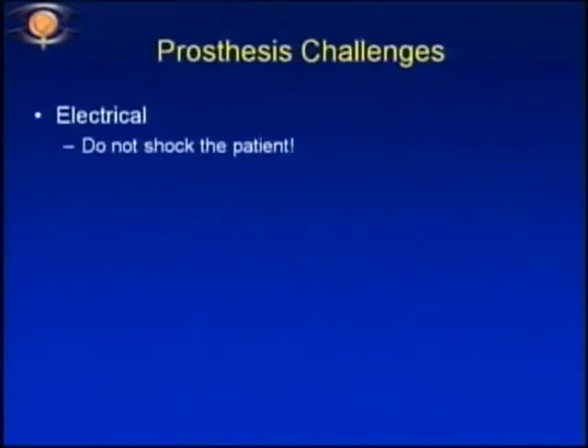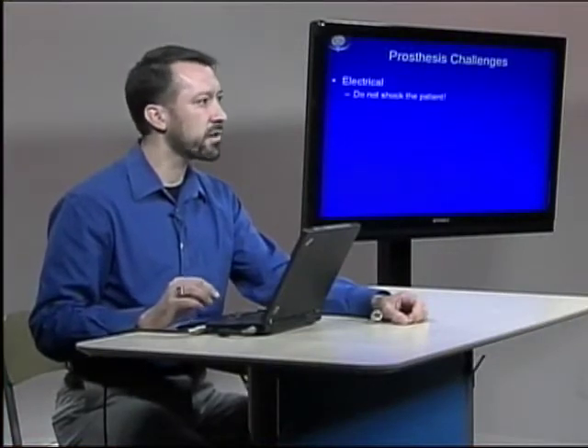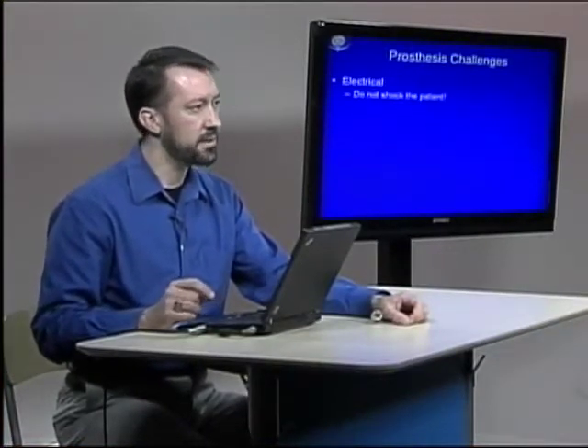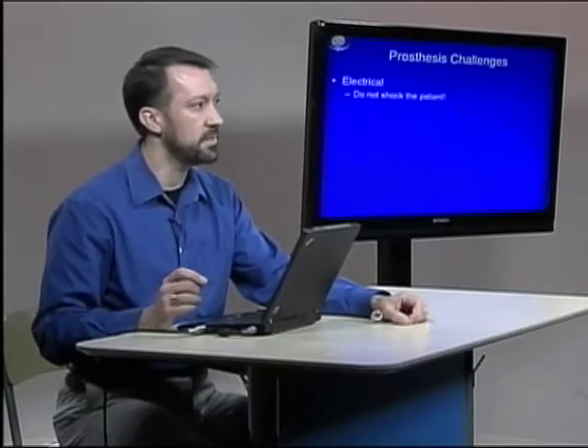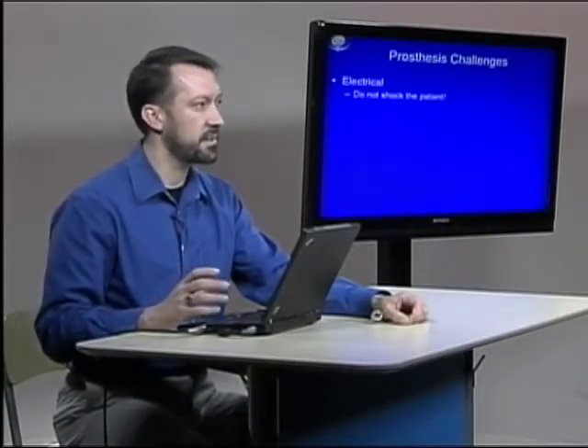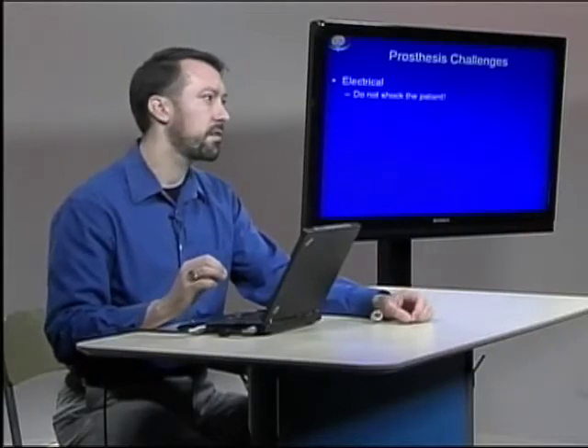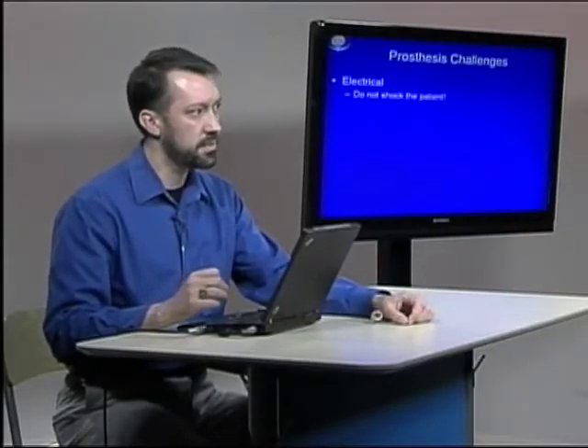This would seem to be fairly obvious, but there are a lot of ways that things can go wrong, a lot of ways that an engineer might not think about that can really cause some damage to the patient. So we have to think about what kind of failure modes can happen and try to build in extra safety features that can try to protect against those failure modes. If one thing goes wrong in your implant, you can't allow that to cause damage to the implant or to the patient. You need to be able to accept one mode of failure and have a separate safety feature that protects against it.